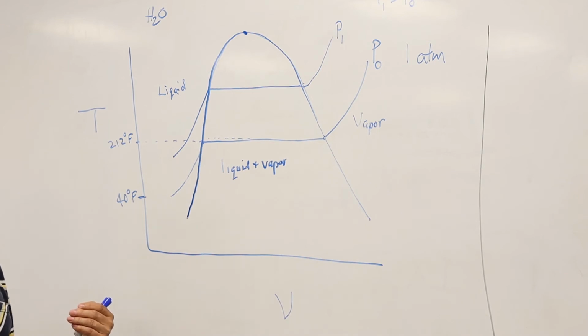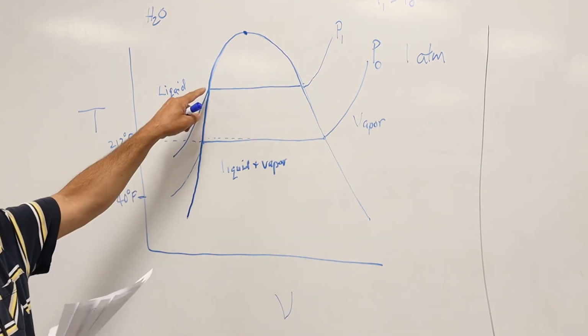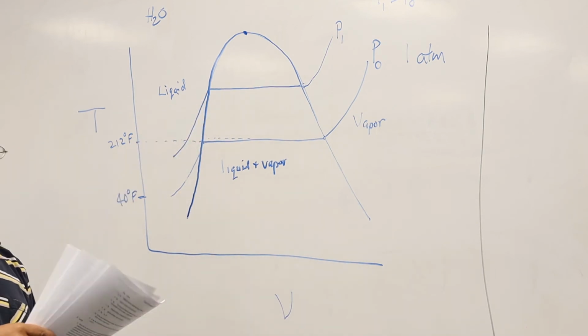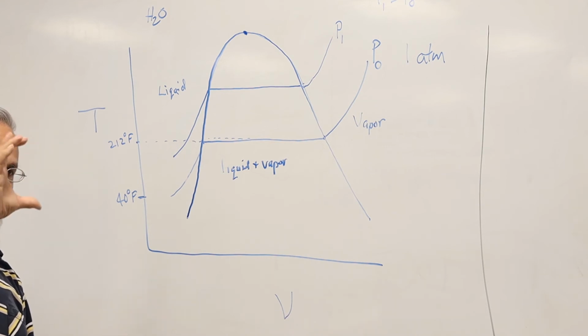I'm glad you said that because that's often confusing for students, because subcooled invokes other visual ideas. In the simplest form, if I know what my saturation temperature is, where I'm going to start transforming liquid into vapor for whatever given pressure, however much I'm below that temperature, that amount of delta is actually the amount of heat I'm missing.